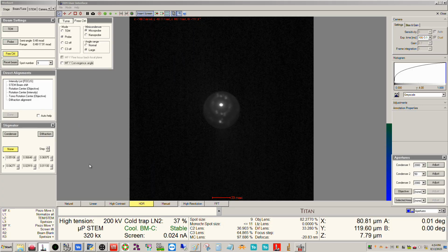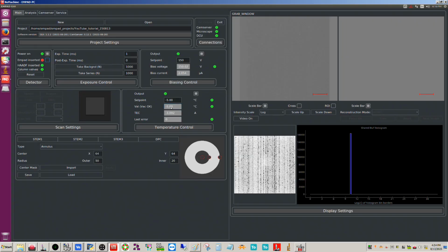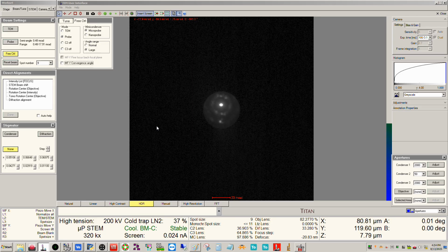Again, you want to use a high enough camera length for that. And how are we doing here? We're almost at the set point here. I think I've covered doing that in previous videos, so I'm not going to go through that again. But my experience is that this is actually closer to about 1 millirad than half a millirad.